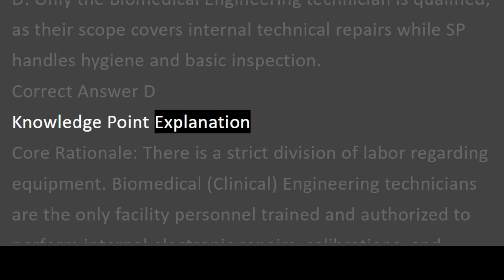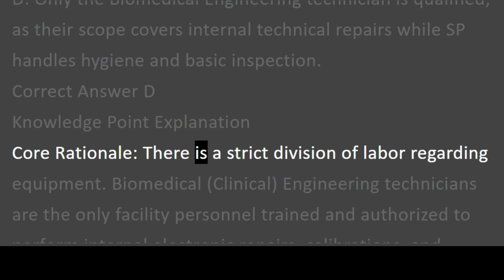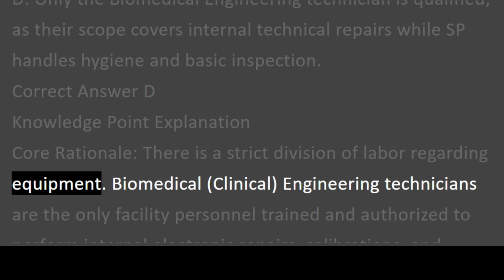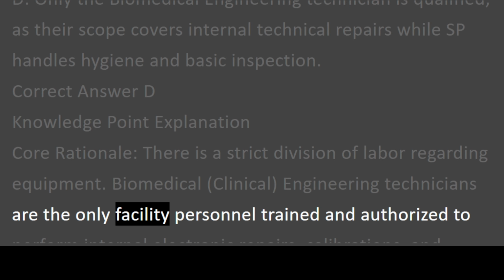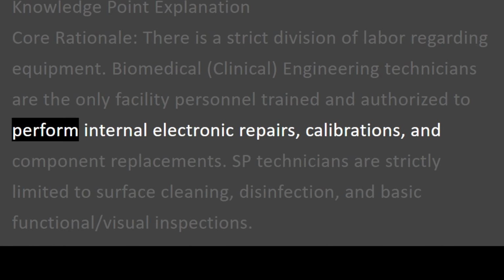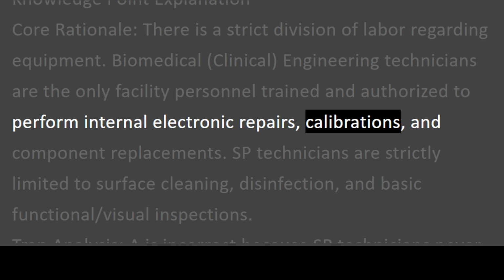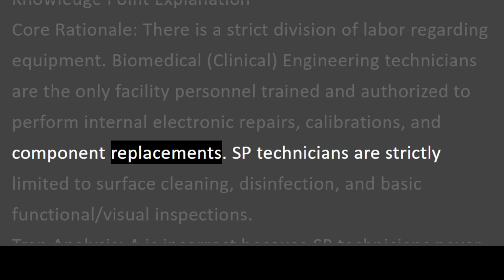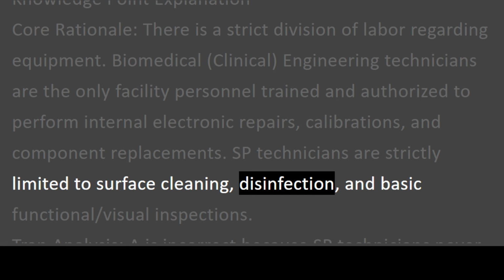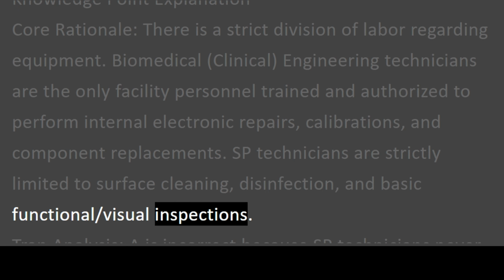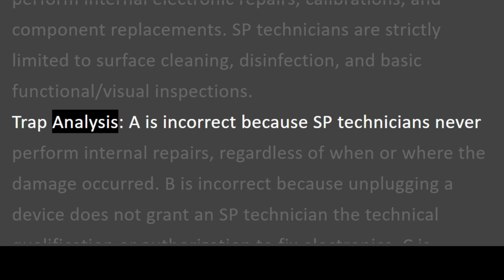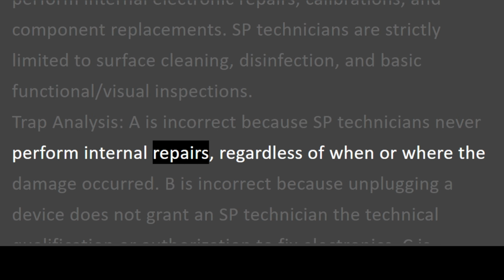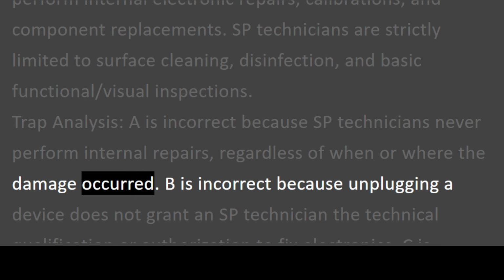Knowledge point explanation. Core rationale. There is a strict division of labor regarding equipment. Biomedical, clinical engineering technicians are the only facility personnel trained and authorized to perform internal electronic repairs, calibrations, and component replacements. SP technicians are strictly limited to surface cleaning, disinfection, and basic functional and visual inspections. Trap analysis. A is incorrect because SP technicians never perform internal repairs, regardless of when or where the damage occurred.